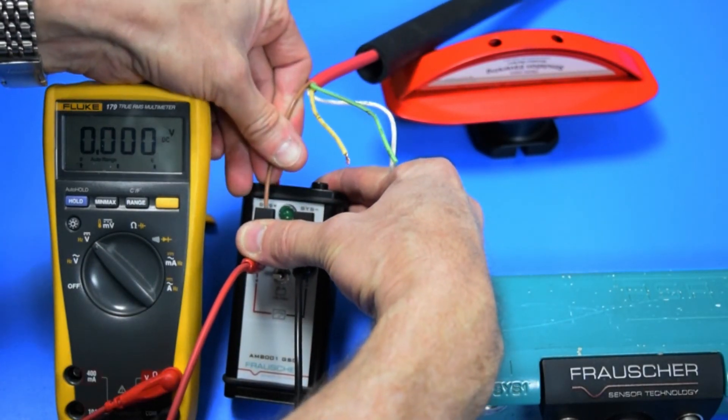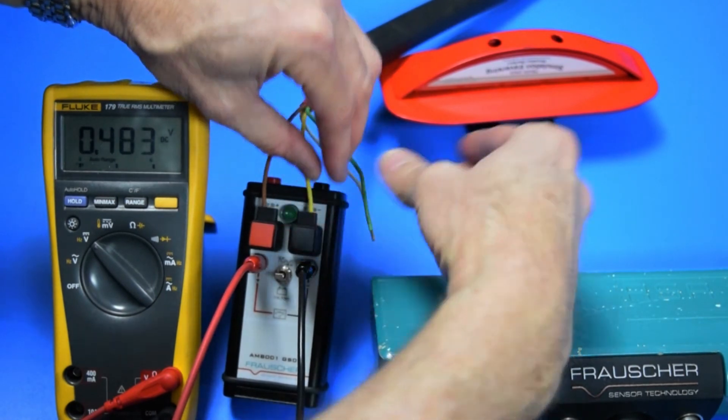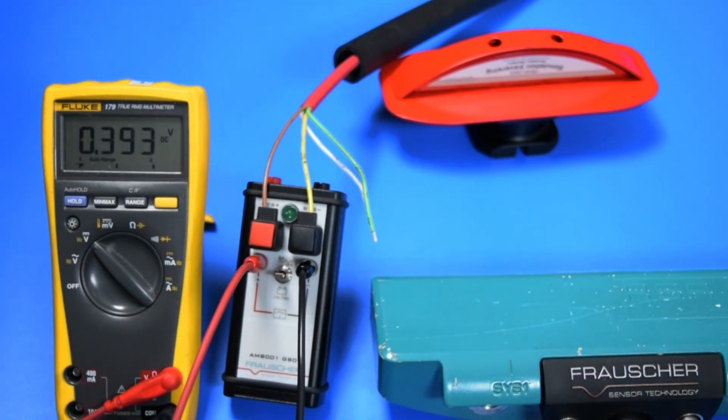Next, attach the transducer wires from sys 1 to the AMB. The brown wire goes into the red sys positive terminal and the yellow wire goes into the black sys negative terminal.